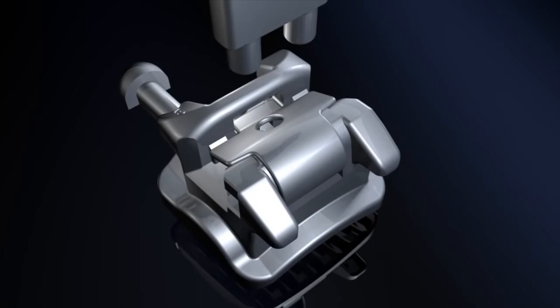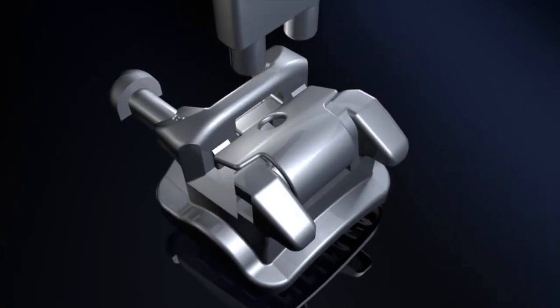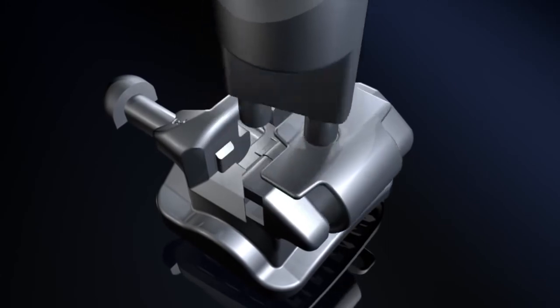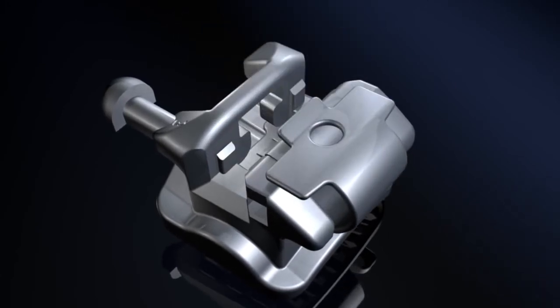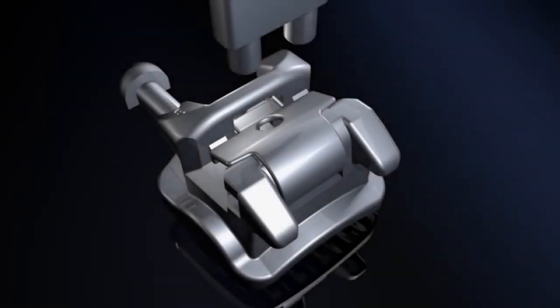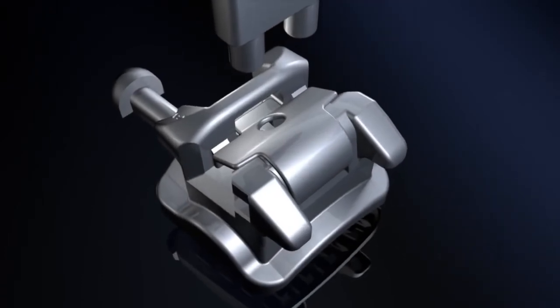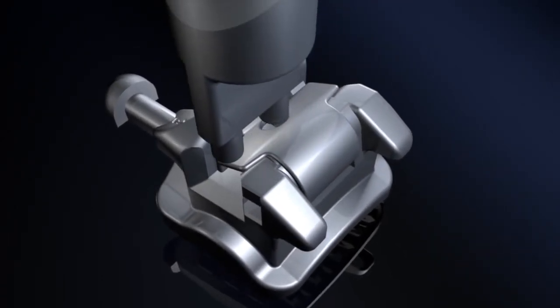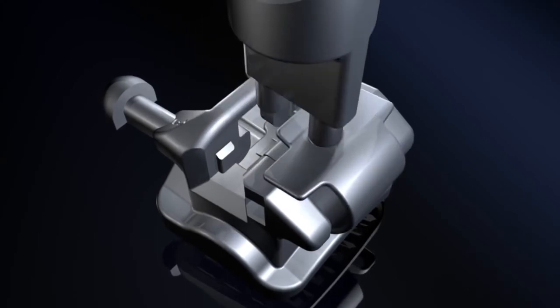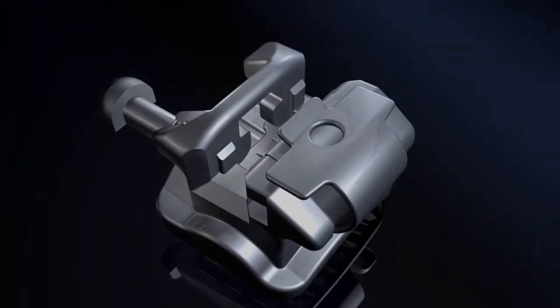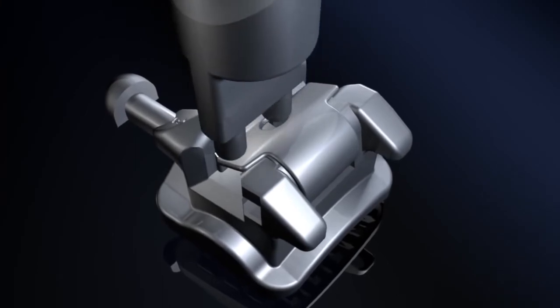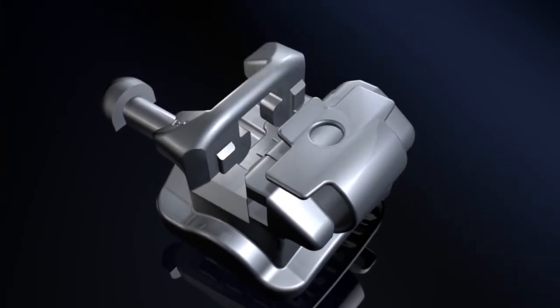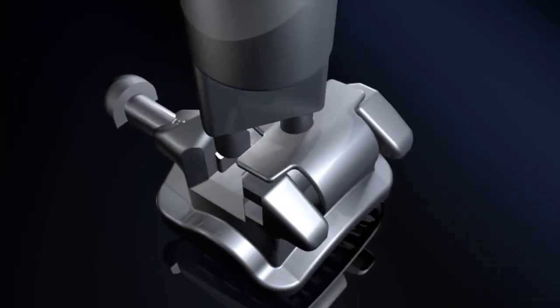The new two-pronged probe can be used to open the clip by rotating the probe. The advantage of this is that the force exerted is restricted to the bracket body clip system and is therefore more comfortable for the patient. To open the clip, insert one of the two prongs of the probe into the hole of the clip. The other prong should rest next to it on the same plane. Now, rotate the probe carefully in the direction of the prong inside the hole. When you do this, the loose prong slides along the gingival bar of the bracket, whilst the other one pushes the clip open.